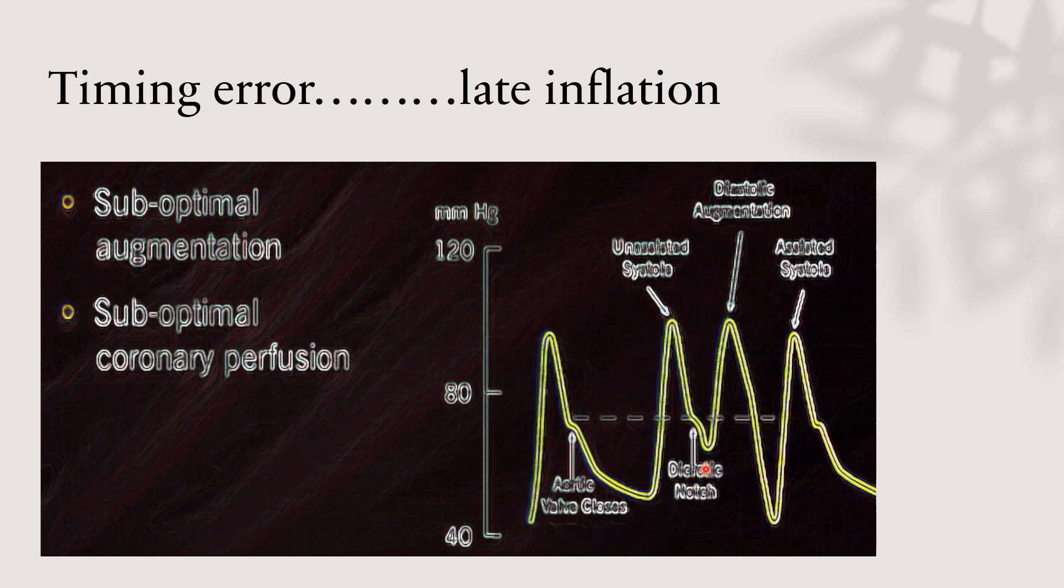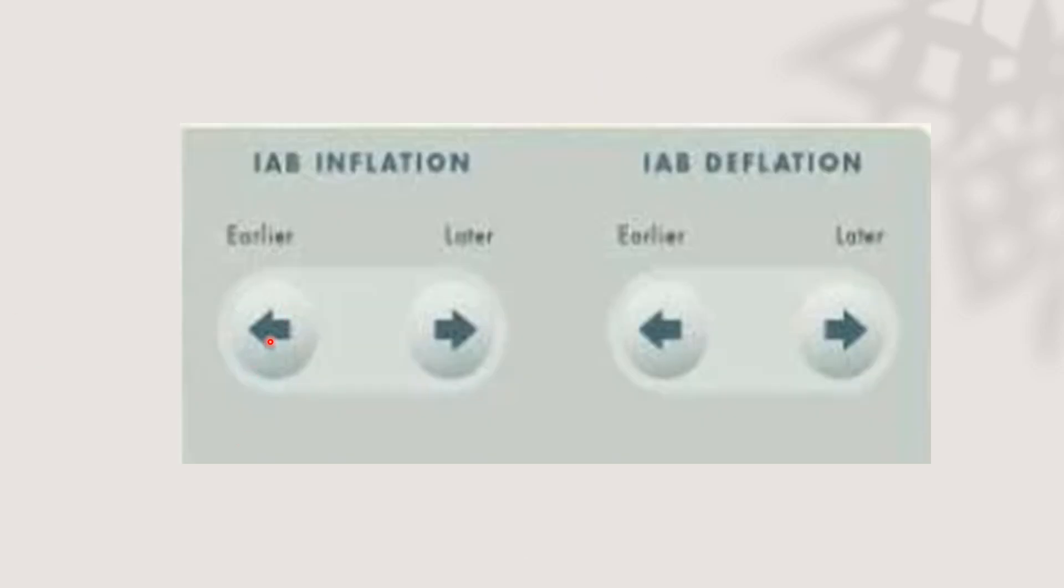The second part is late inflation, and that will lead to suboptimal augmentation. If there's a delay in the inflation of the balloon, it will delay the displacement of blood into the periphery and coronary artery, leading to suboptimal coronary perfusion. We solve the issue by making the balloon inflate earlier till we get the right curve.